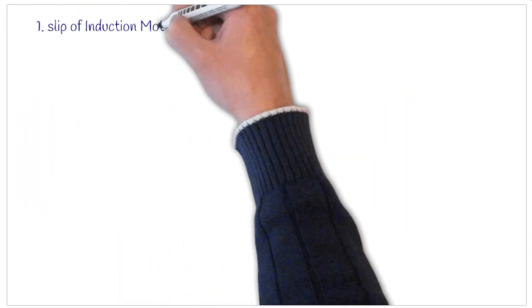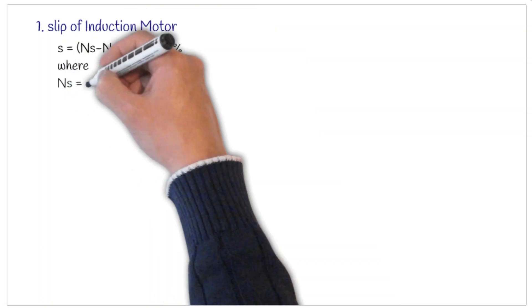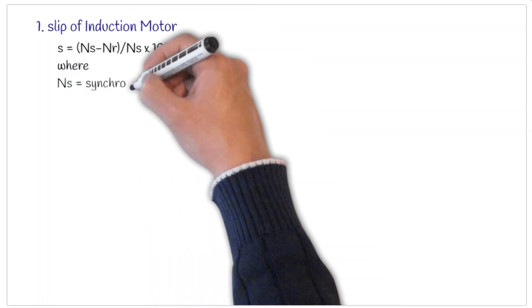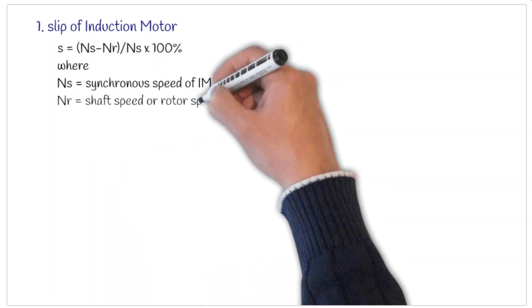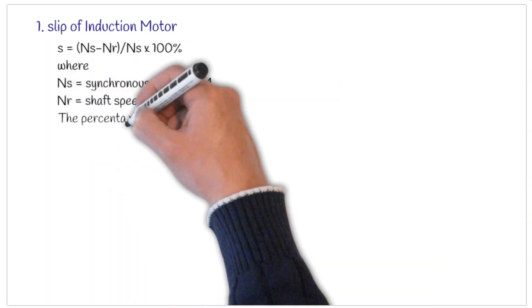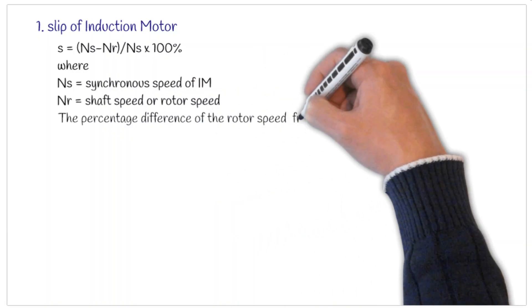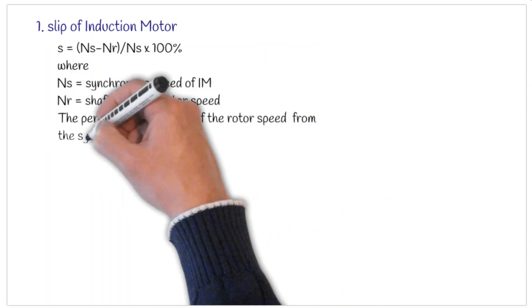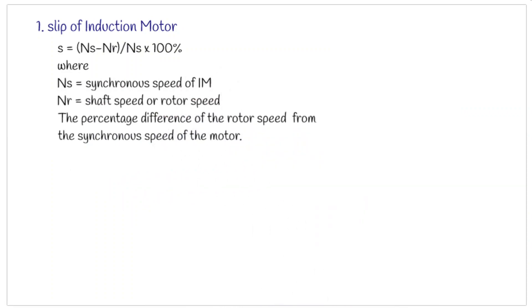Before we understand the equivalent circuit of the induction motor we need to understand two more things. One is the slip of the induction motor. Slip actually represents the percentage difference of the rotor speed from the synchronous speed of the induction motor, where Ns is the synchronous speed and Nr is the rotor speed, given by the equation (Ns minus Nr) over Ns. We will see how this plays a role in the equivalent circuit of the induction motor.